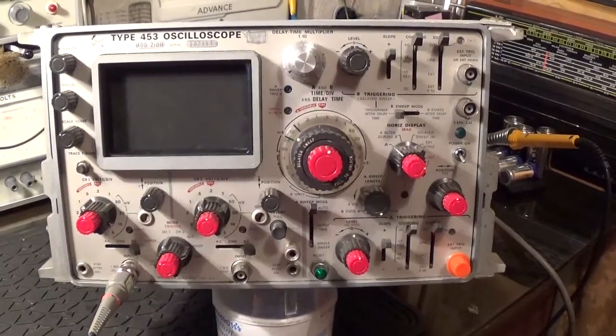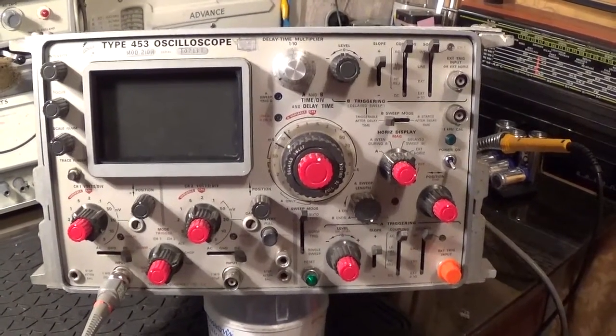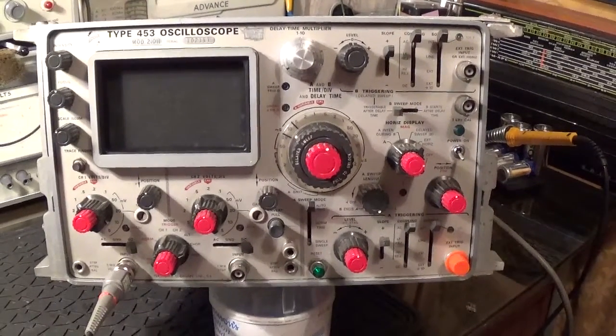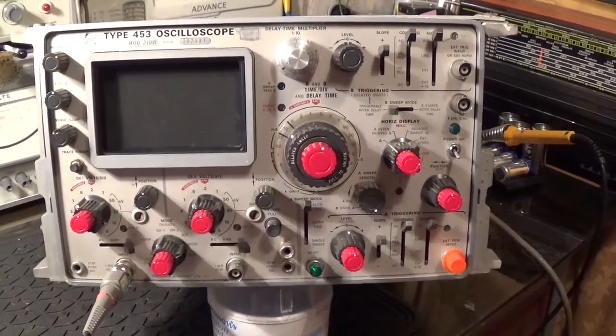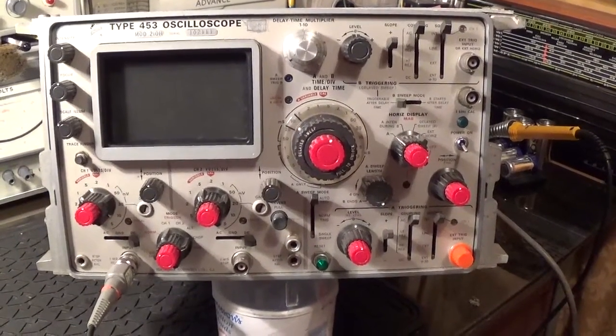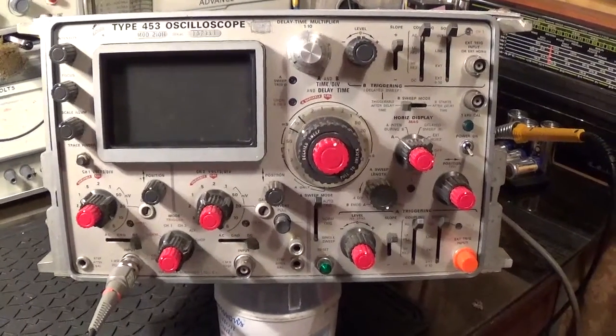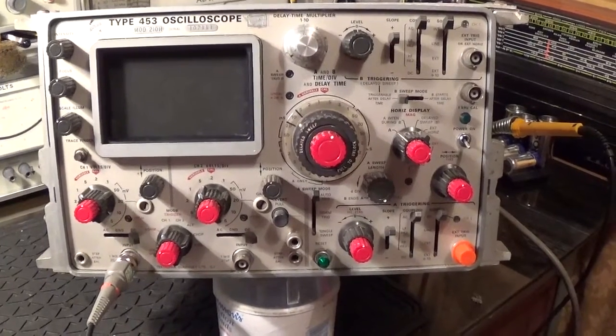I'm glad I did because it had been wired up backwards. Here in the UK, the brown wire goes to the live side which is fused within the plug, the blue lead goes to neutral, and the yellow and green wire goes to earth. The brown and blue wires had been transposed, which is not the greatest really.